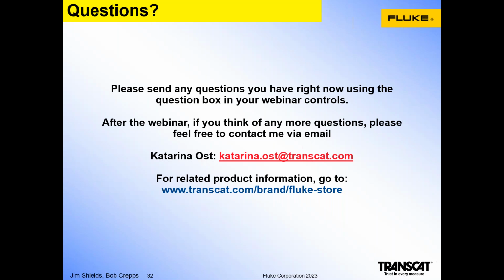Okay. How many calibrations can be documented before uploading back to the calibration software? I'll let you take this one, Bob. Sure. We try to be conservative about it, but you can actually do at least 50 calibrations on the calibrator. Generally in a given day, a super tech like Jim could probably do 10. But generally, 5 or 7 per day.